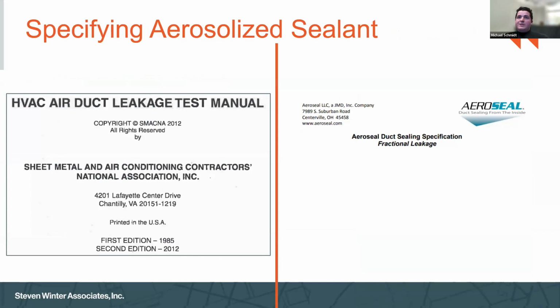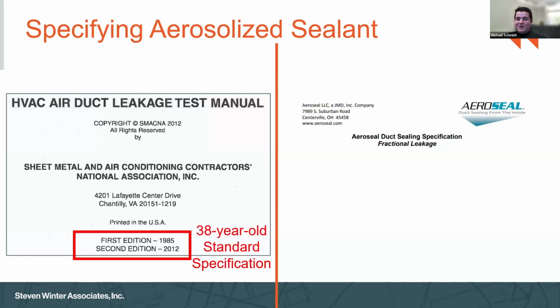Now, I did want to mention specifying AeroSeal. If you're working on passive house projects and you're using aerosolized sealant application as part of the project scope, I would strongly recommend specifying it in a particular way. Essentially, there are two ways you can specify, using the SMACNA standard shown on the left. I just wanted to point out that it is quite an outdated standard, right? It was originally written about 38 years ago. I think that's updated to 39 now. But the standard is old and is essentially inadequate for high performance buildings to reach the low levels of duct leakage that we'd like to target.